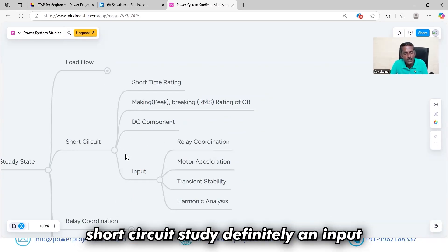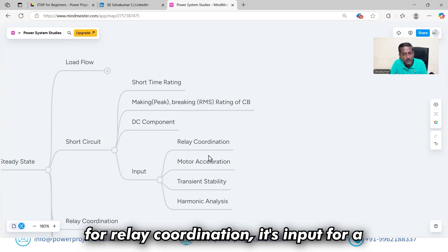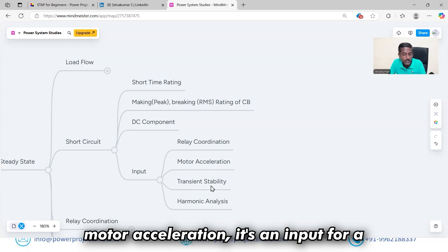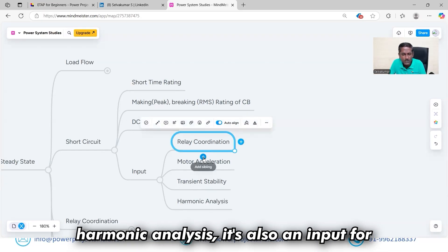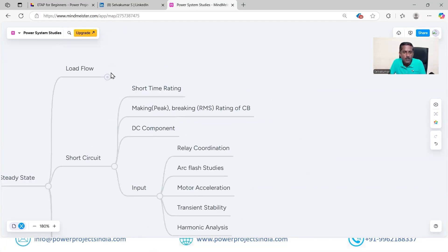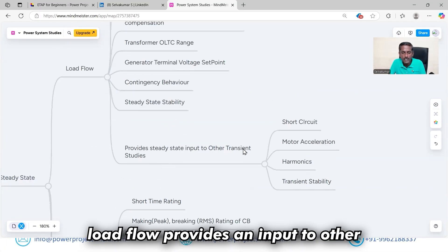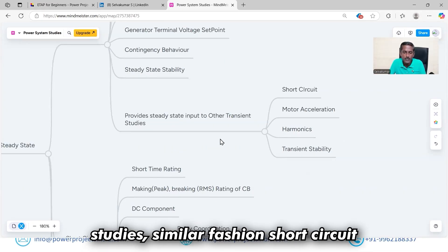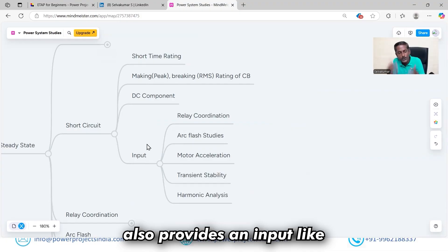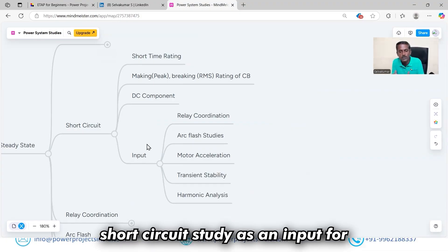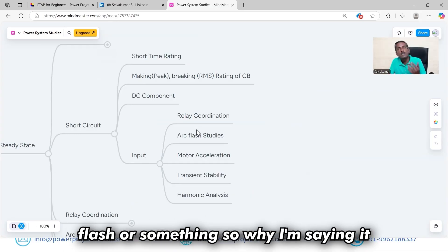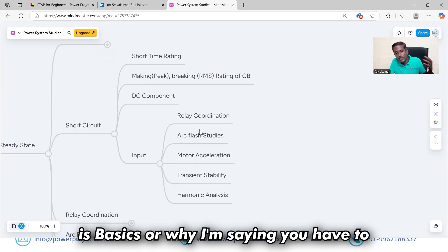Short circuit study is definitely an input for relay coordination, motor acceleration, transient stability, and harmonic analysis. Just as load flow provides an input to other studies, short circuit also serves as an input to other studies like relay coordination and protection.